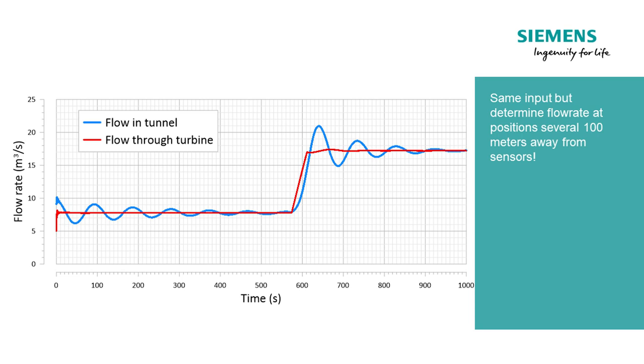In that way we can actually provide information about the flow oscillations in the tunnel system, and those flow oscillations are the main reason for lifting and transporting rocks. Using Simcenter Flowmaster, we provide the operator a good measure for what type of transients are allowed during operation, and we can provide answers on how to minimize flow oscillations — perhaps by adjusting the opening ratio stepwise.